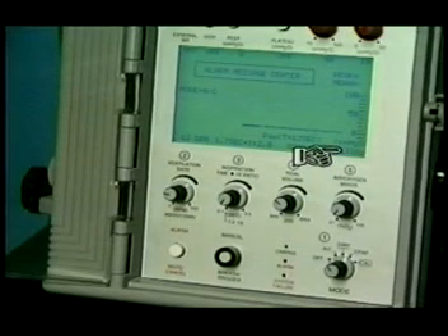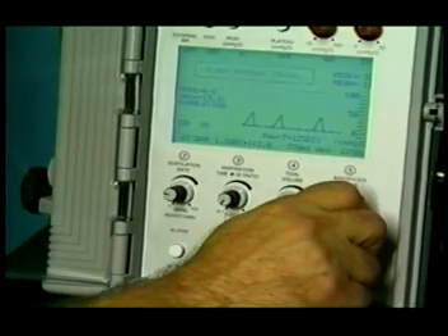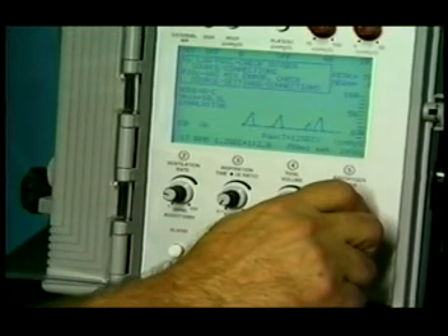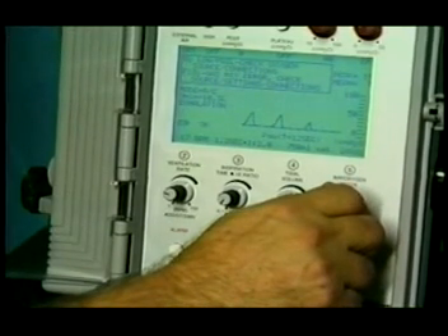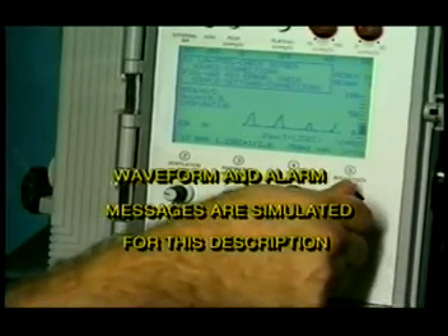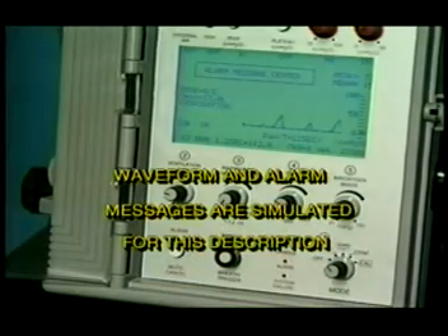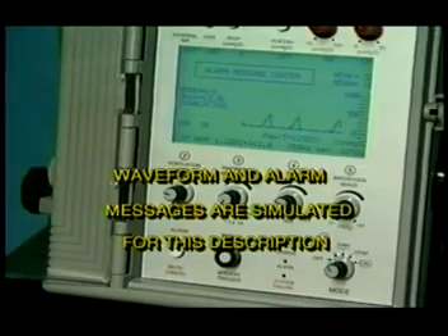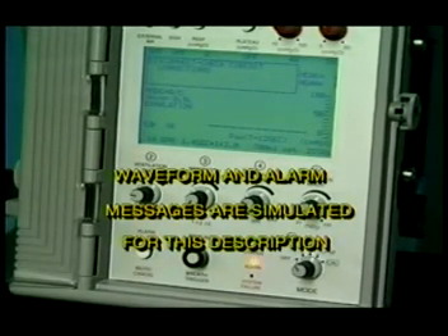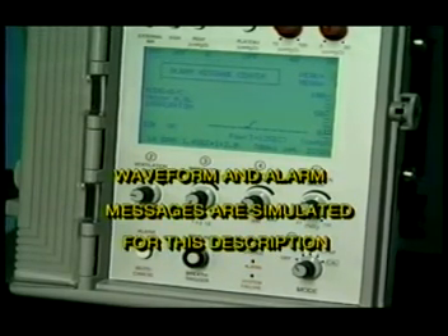Because oxygen is connected, our air oxygen mixer range can be set anywhere between 21 and 100%. If oxygen was not connected, disconnected, or if our oxygen cylinder was empty, turning this control would trigger an oxygen alarm at all settings greater than 21%. We can cancel this alarm by returning the control set point to 21%. Verify all control settings to ensure their accuracy. By now, you will have noticed that the ventilator has begun cycling and that a disconnect alarm has occurred. Connect the ventilator circuit to the patient, which will cause this alarm to self-cancel.